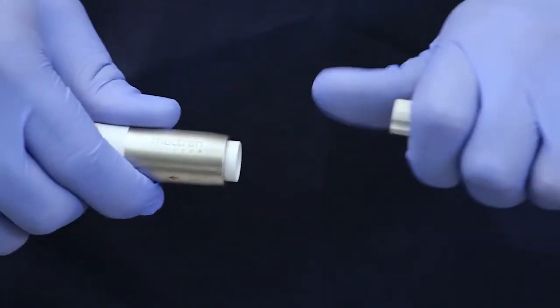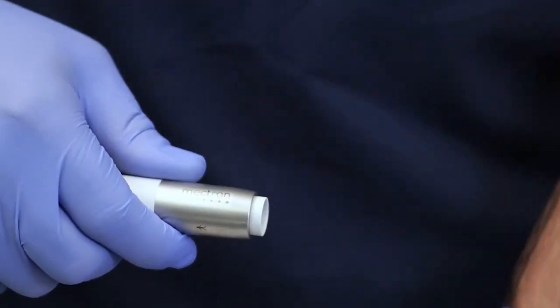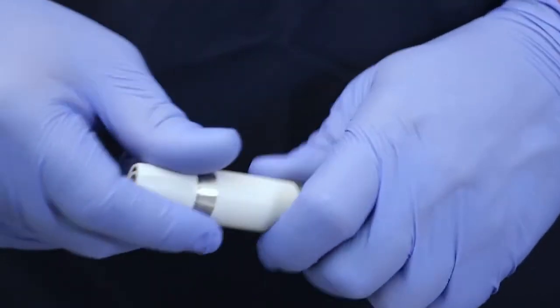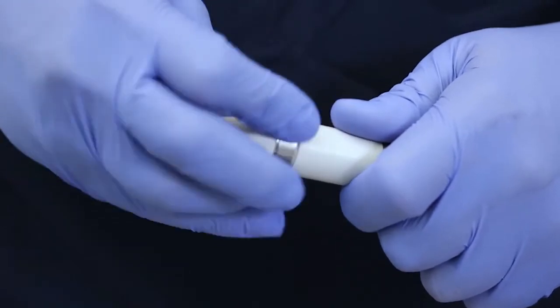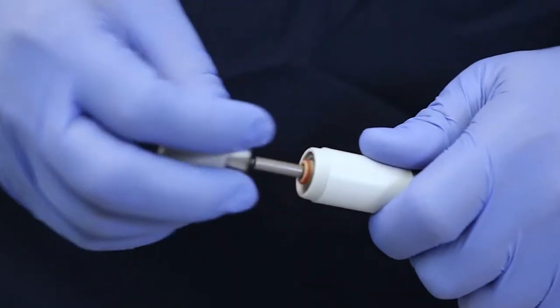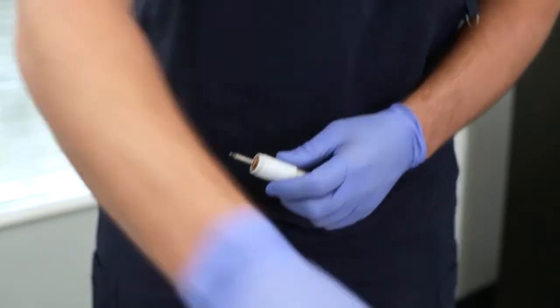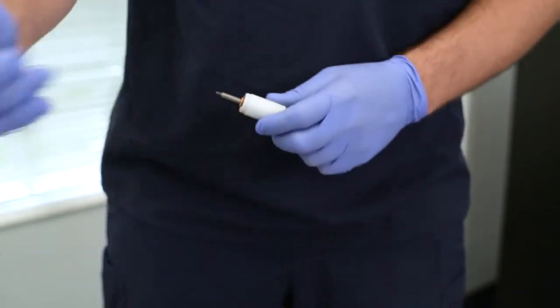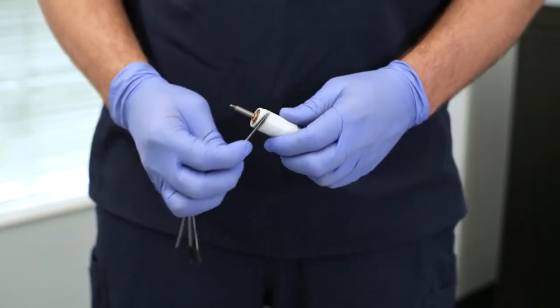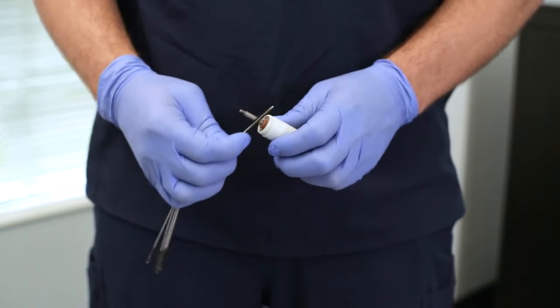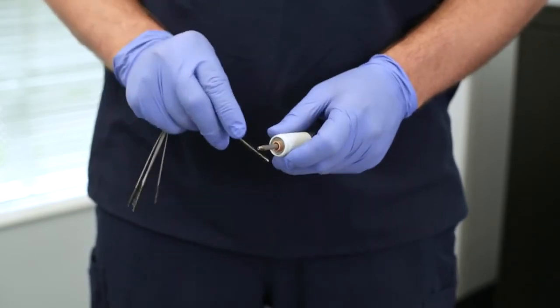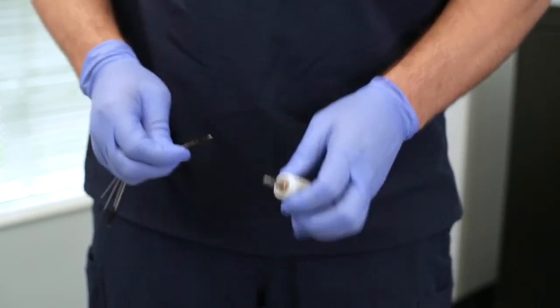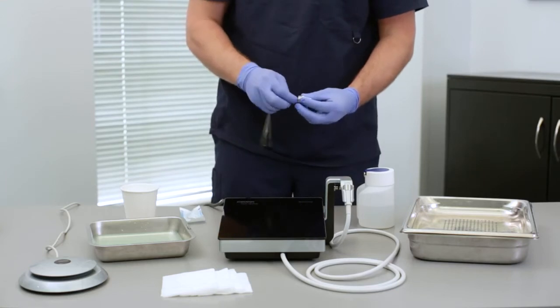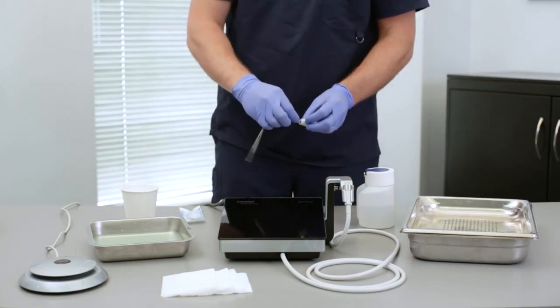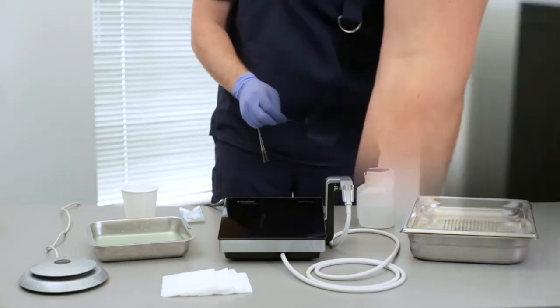Next, disconnect the handpiece from its cord. Upon removing the handpiece from the cord, also remove the LED cone by unscrewing it from the handpiece using the silver metal ring. With a soft bristled brush or towel, clean all of the components with the enzymatic detergent until all visible debris has been removed. Pay close attention to the threaded pin the inserts screw onto, the visible parts around the pin, and both the internal and external parts of the LED cone.